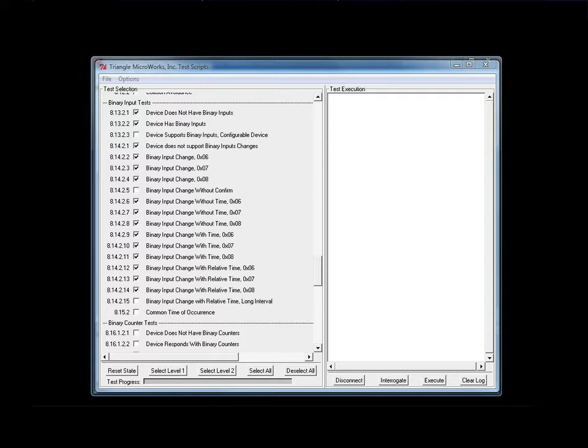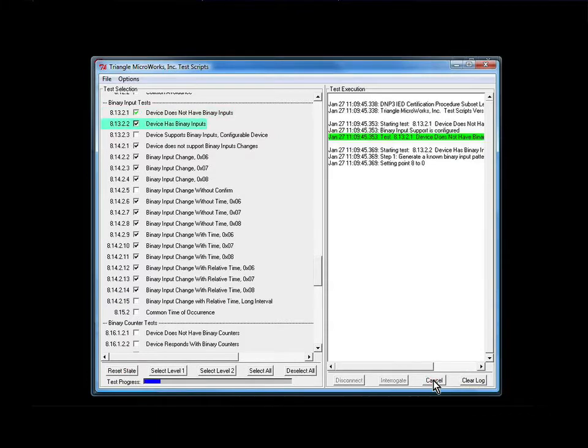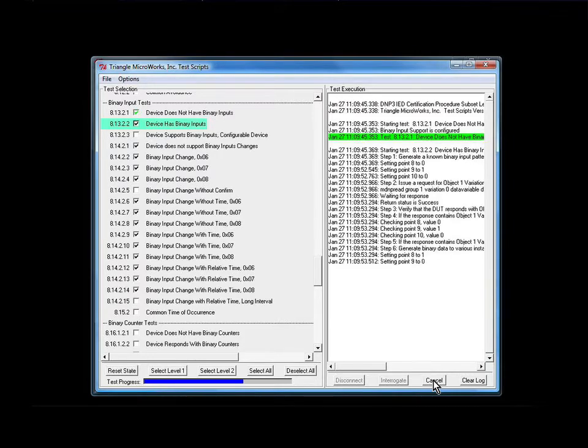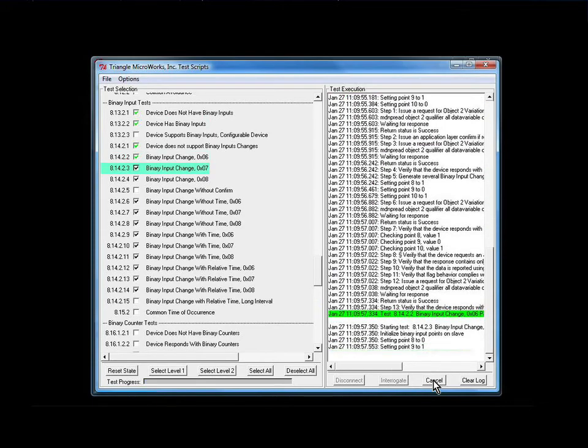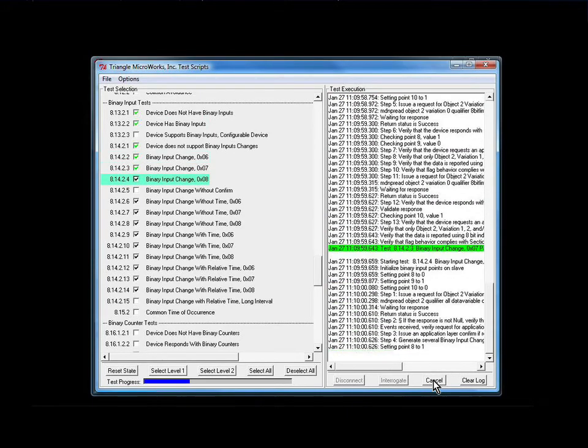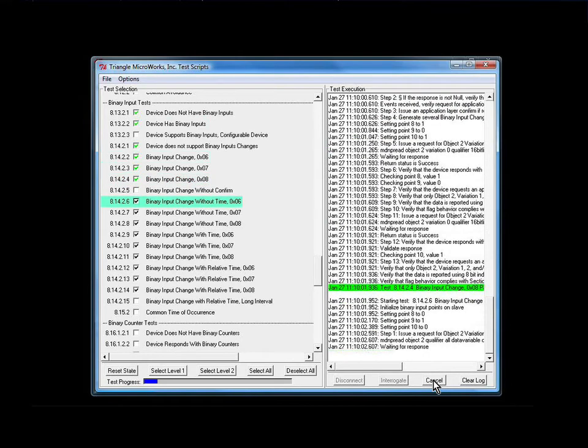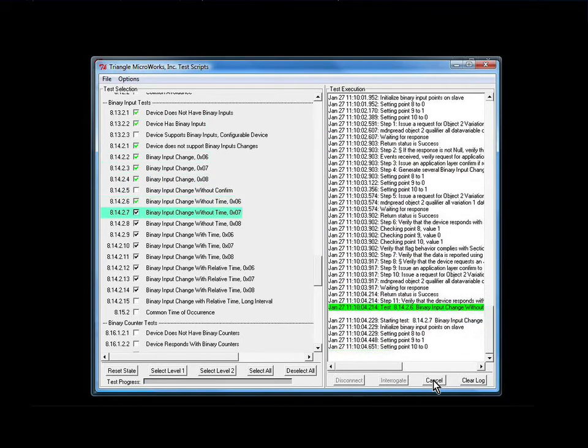For the double-bit binary test, we don't have automated test equipment connected. To run the test, start by resetting the state in case any tests have previously been run, and then simply select Execute. The test begins, and in the right-hand pane it shows the tests that are running, displaying a green band as each test passes, or a red band if the test failed. This is a fun test to run in person because you can hear the Omicron fire up and the relay start clicking.